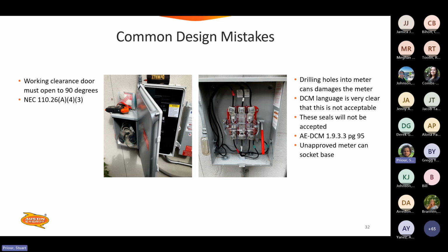Also, using unapproved meter cans. So you're going to have a 200 amp meter can with a bypass handle. If it's not that, it's not approved. If it is one of those, it's still not necessarily approved. You need to look at the list and make sure that the exact make and model is on the approved list for your service voltage.